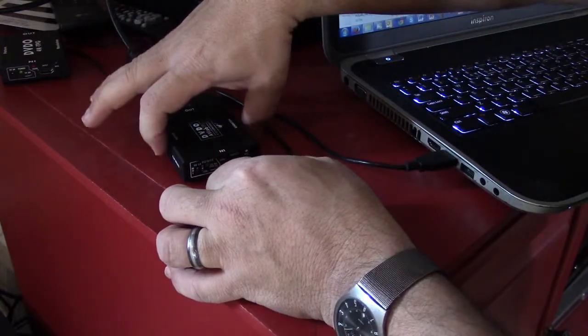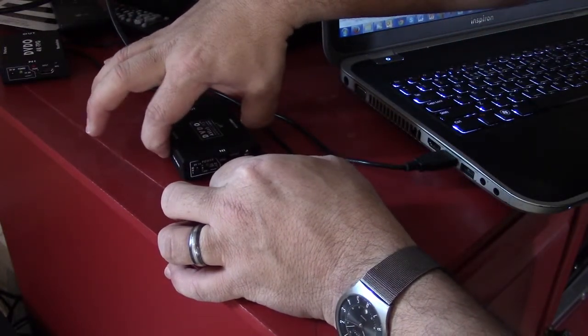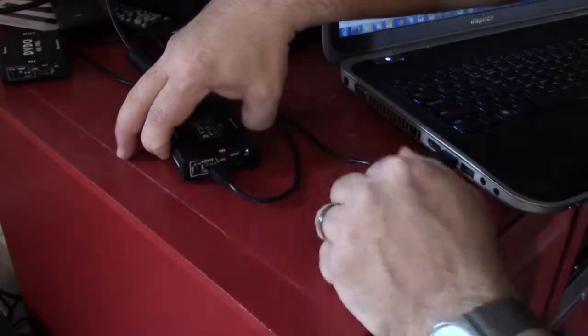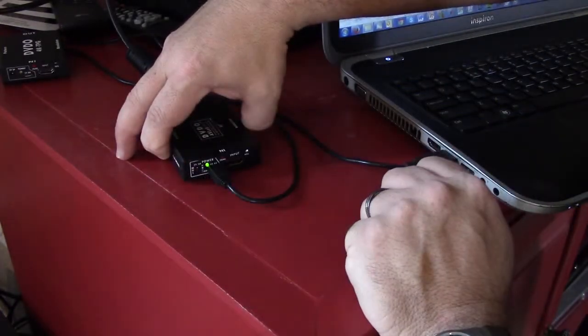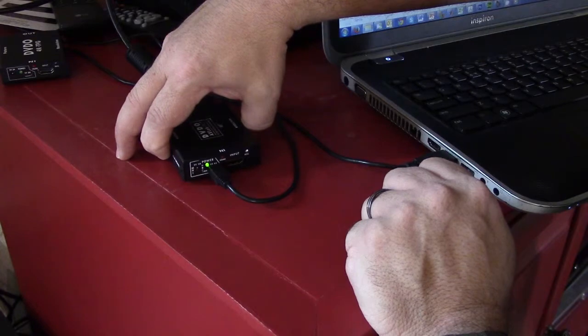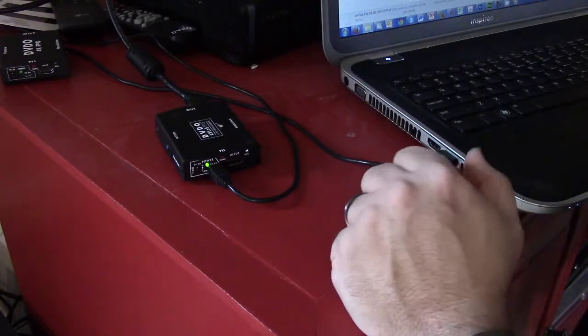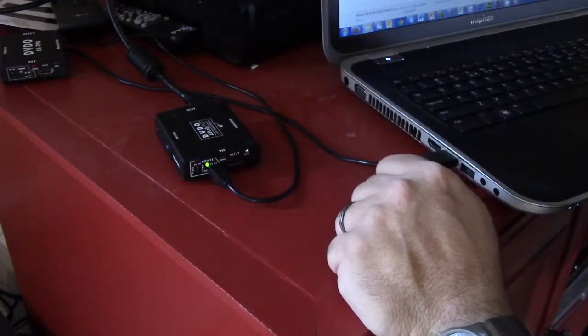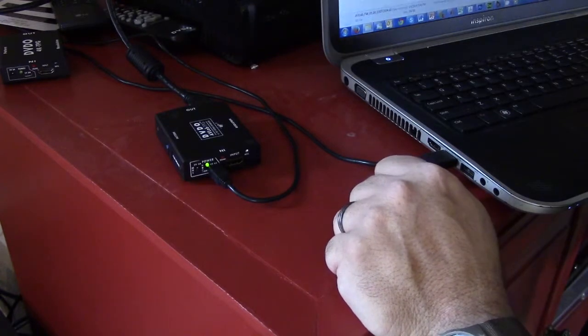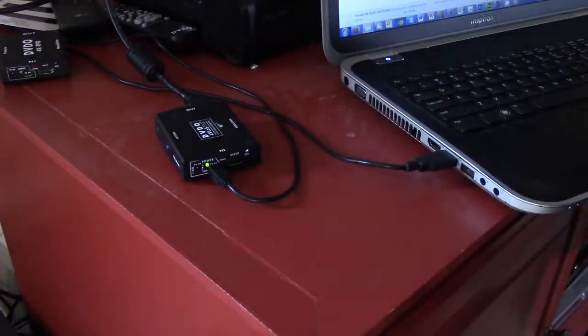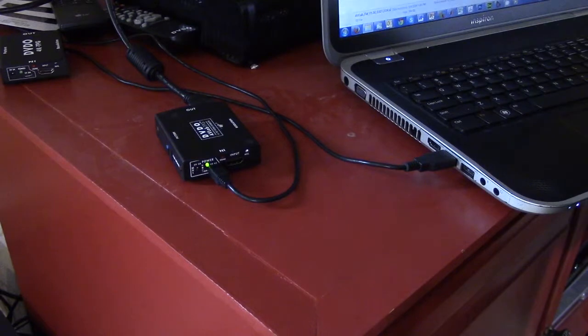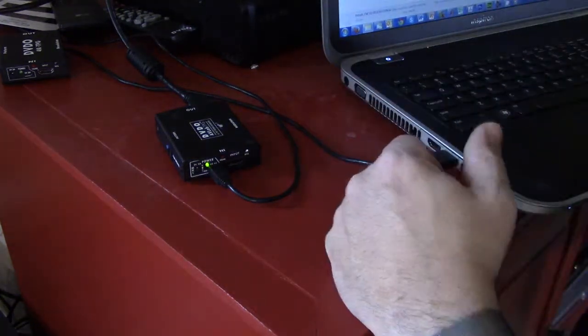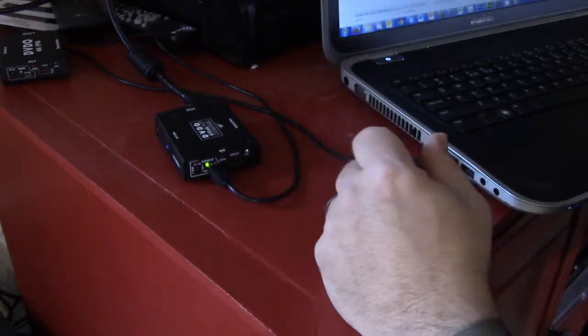Hold down both the pattern and the resolution buttons together. While we do that, plug in USB. Give it just a second, then release both buttons. What that does is reset everything in the test pattern generator to factory default - all the resolution, all the pattern stores, everything gets reset to work properly with the new firmware. We do suggest you do that.